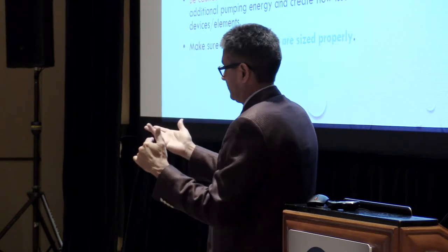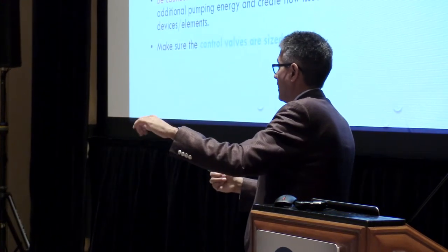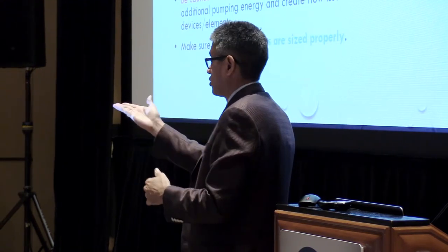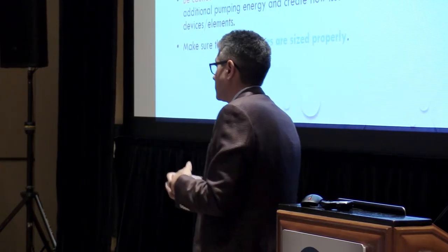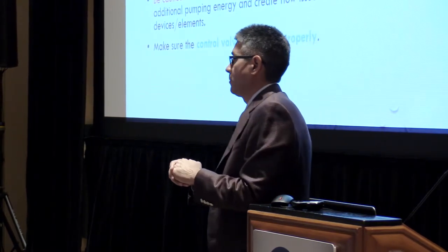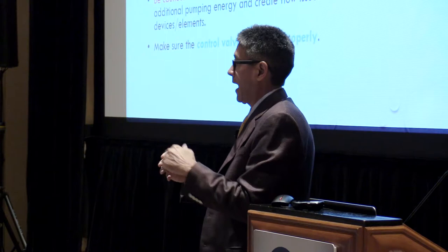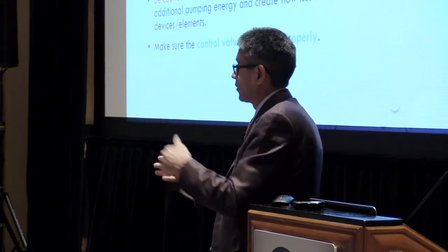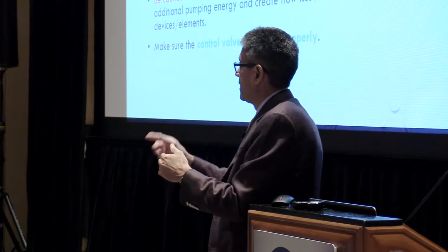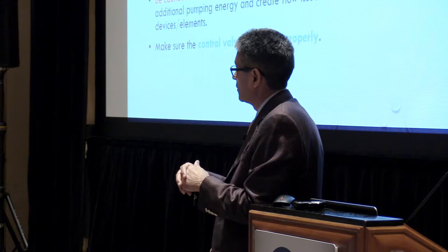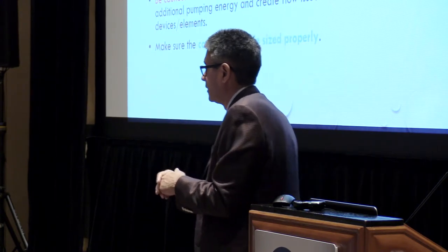The pressure is too high leaving that automatic flow limiting device. So ironically, to get rid of the problem, if you just throttle down the isolation valve in front of it, decrease the pressure, it's usually the ones closer to the pump or right off the main. That's where you usually see that problem. Some of the AFLDs have a valve in front of them on that side, and if you throttle that down, you'd bring that pressure down. Basically, it's got too high a pressure going into the control valve is what the problem is, and it starts hunting the control valve and you get a chatter.